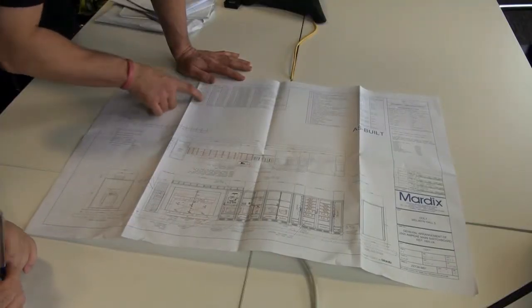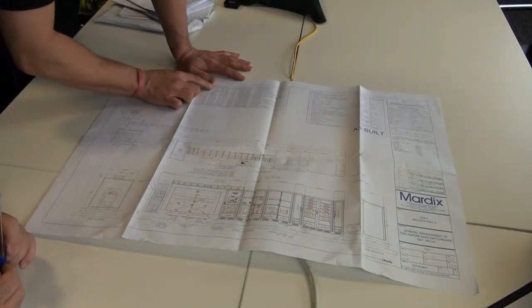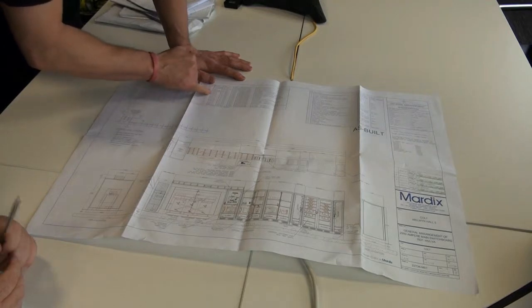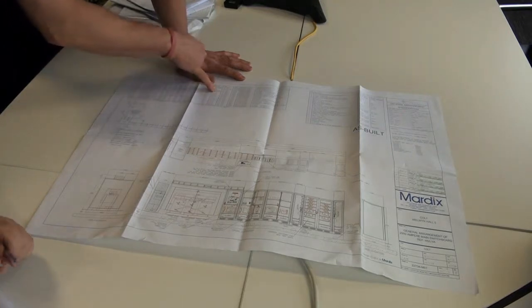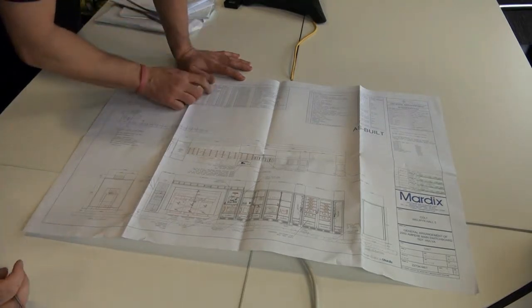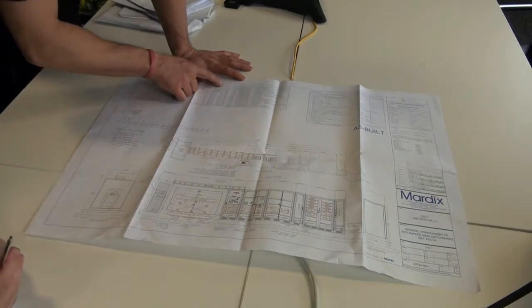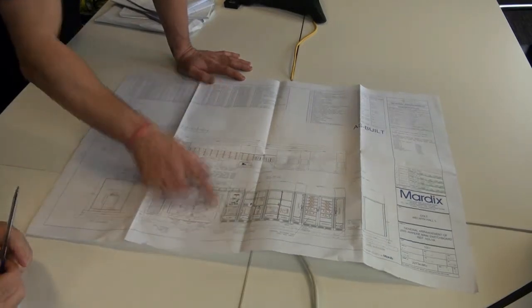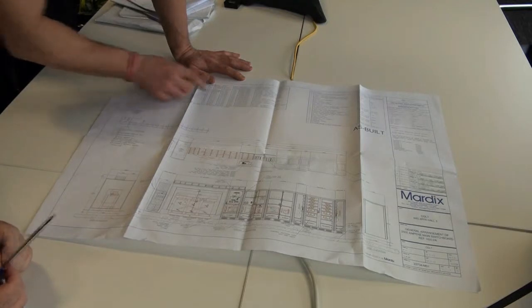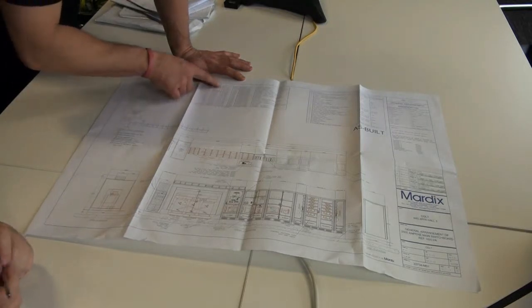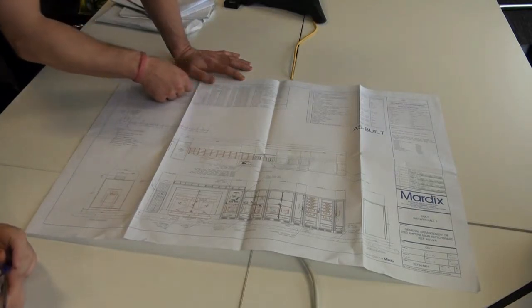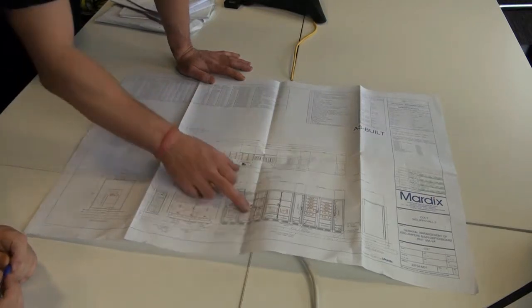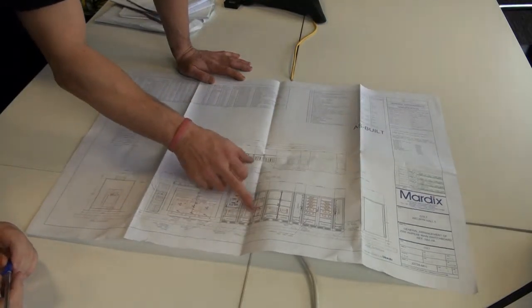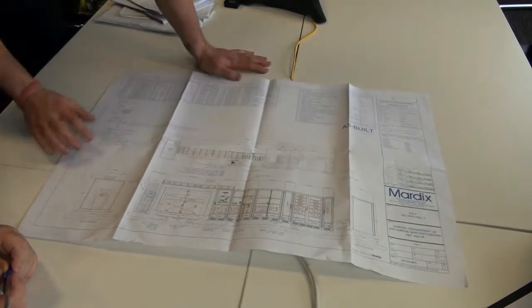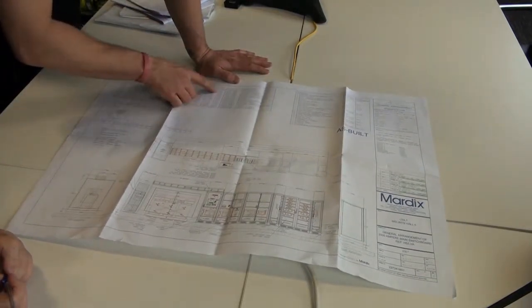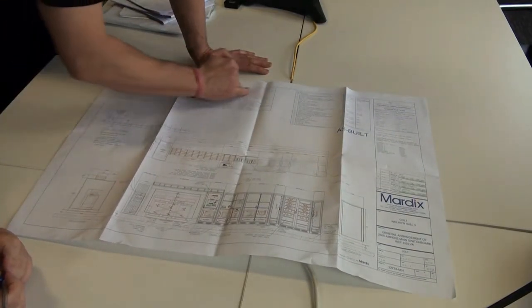Your breaking capacity there, withdrawable, fixed, plug-in. Most of them are plug-in. Again, that will be obvious when you come to the breaker, whether it's withdrawable or not, because it'll have a handle and whatnot. And then whether the device is an auto ACB: if it's an auto, it will have a Micrologic and those settings. If it's a non-auto, then it won't have anything. Non-auto will be A2, which is your generator breaker there. I'll show you the difference between them when we go around there. And then it just carries on and gives you a complete list of everything that's on there.